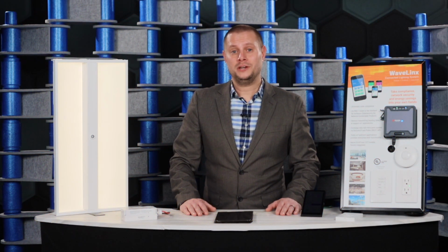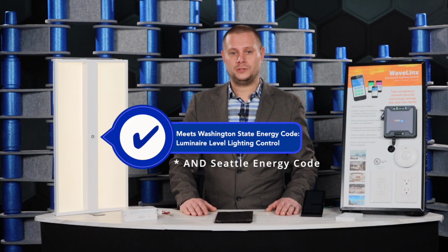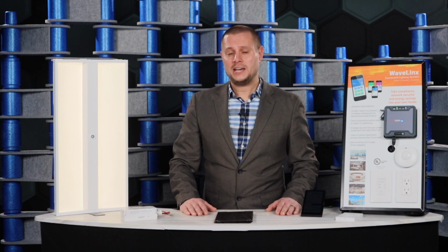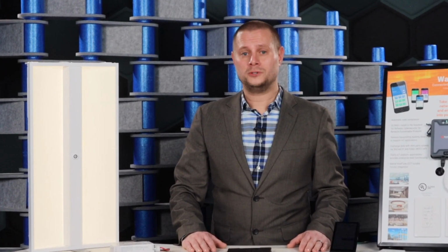Designing with the WaveLinx integrated sensor automatically meets Washington State Energy Code's luminaire level lighting control requirements. On top of that, you can get a rebate of up to $75 from the local utility, which almost pays for the sensor itself.